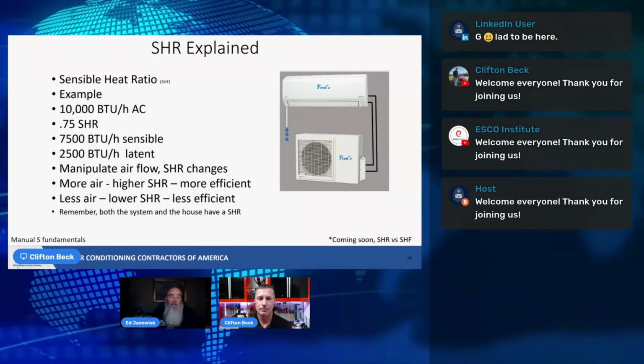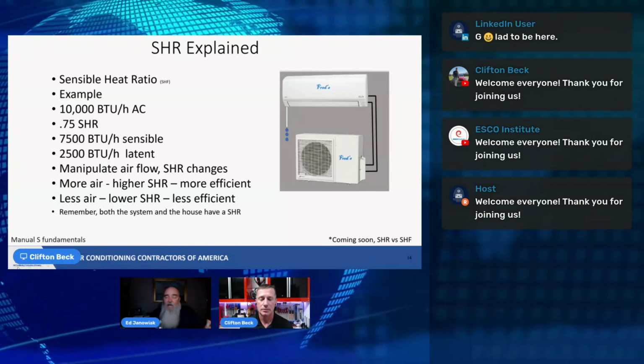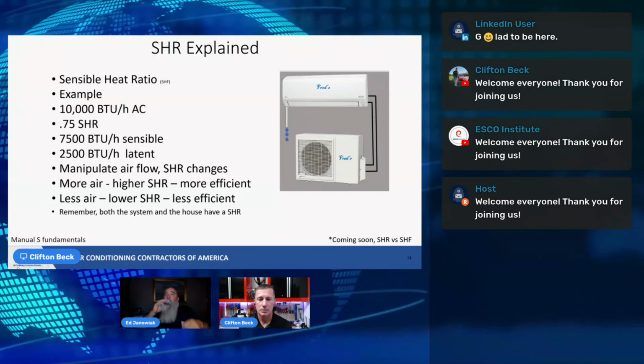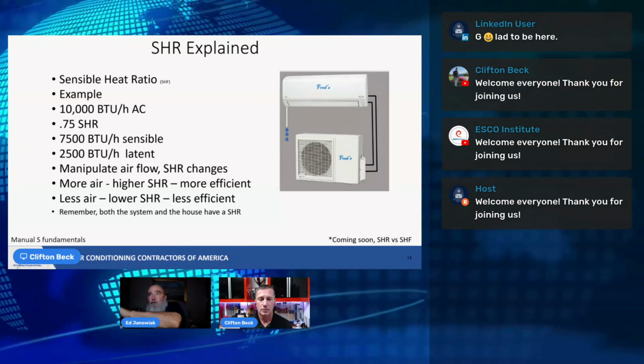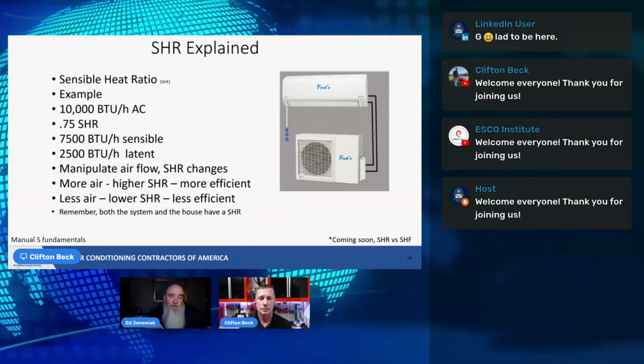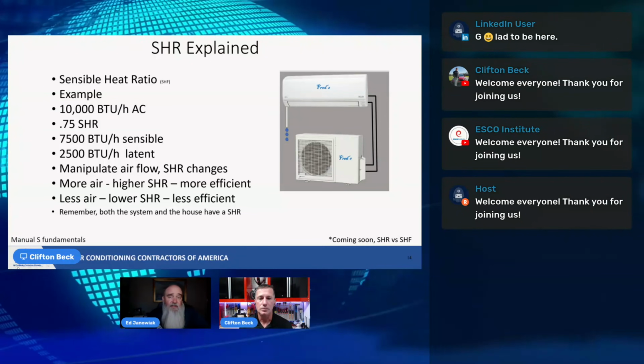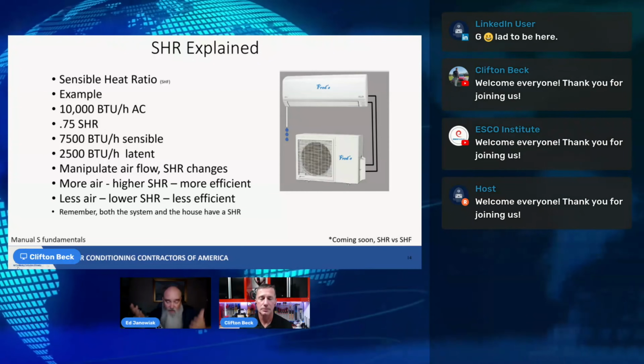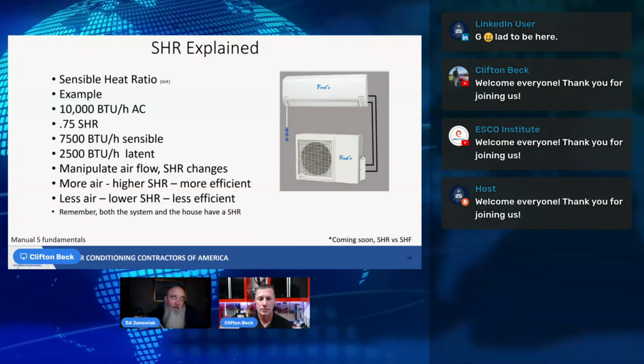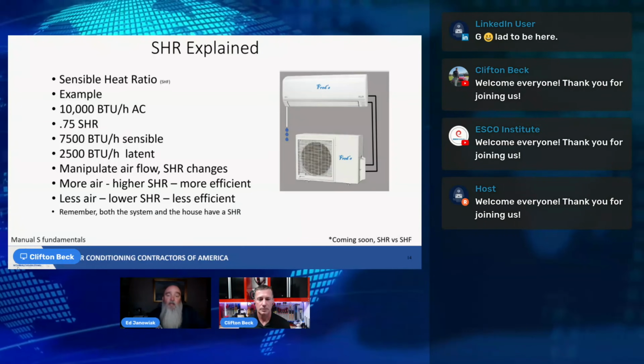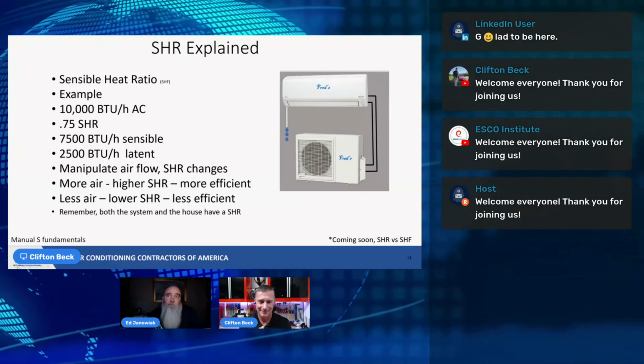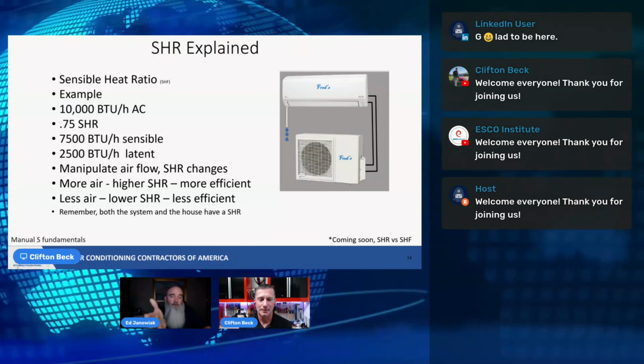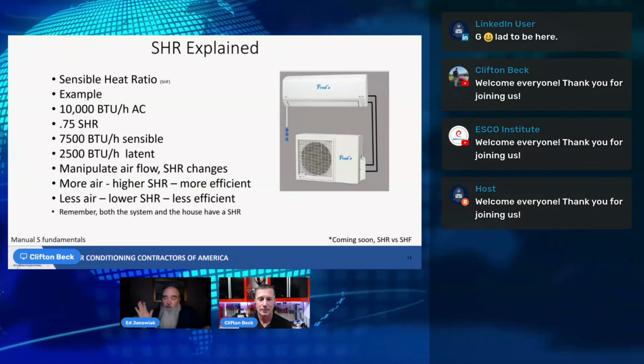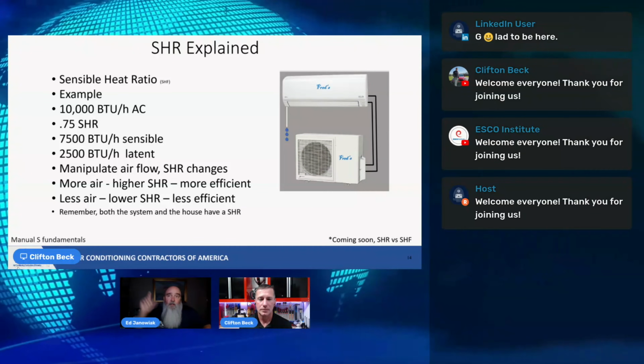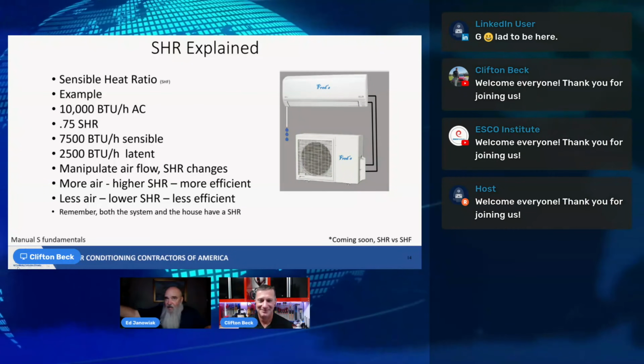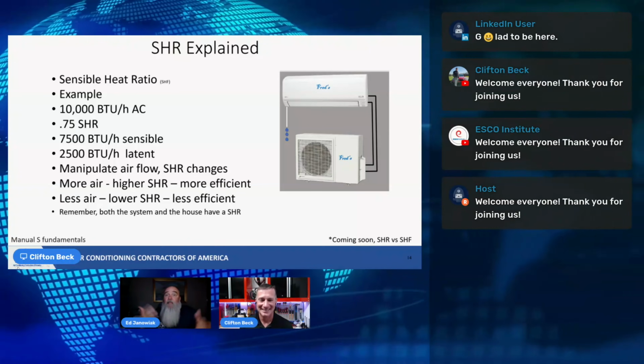I'm not against those things as long as they come from good mathematical practices, but that's what we're talking about here. And we got a piece of equipment where 75%, or 7,500 BTUs, of its total capacity is dropping the temperature of the air. The other 2,500 BTUs are condensing water vapor out of the air. Now, the cool thing about this, and you can try this at home if you really want, or if you don't want people to talk to you at the barbecue, look for the white pipe dripping out of the house, get your red Solo cup, and start measuring.